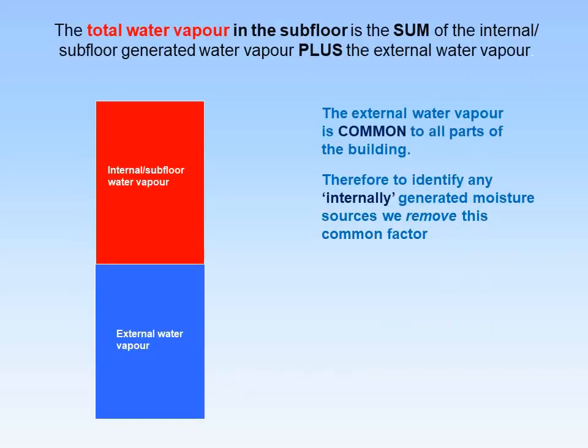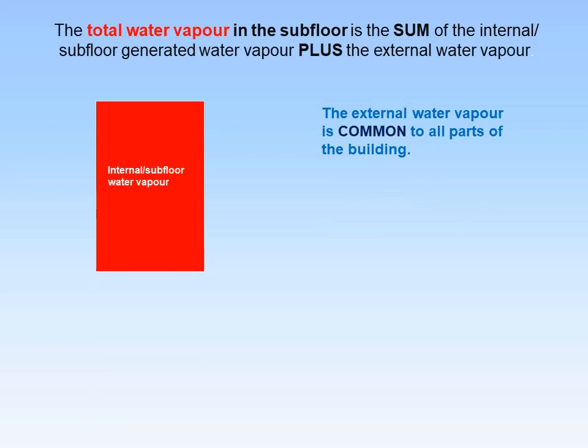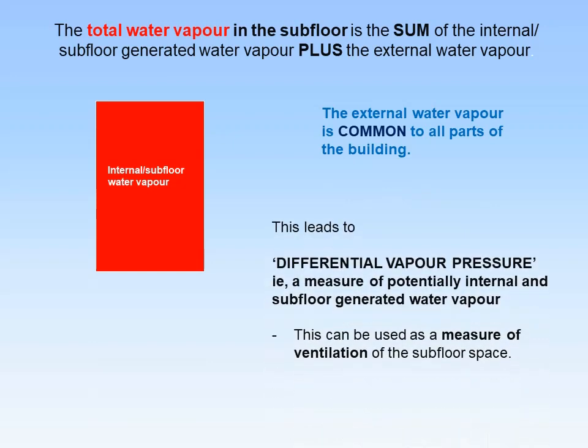The total water vapour in the subfloor void is the sum of two components: the internal levels of moisture plus the subfloor-generated water vapour, plus the external water vapour, as shown in the diagram. Since external water vapour is common to all parts of the building, we remove this common factor from our calculations. This gives us the differential or excess vapour pressure — a measure of potentially internal and subfloor-generated water vapour only, usable as a measure of subfloor space ventilation.